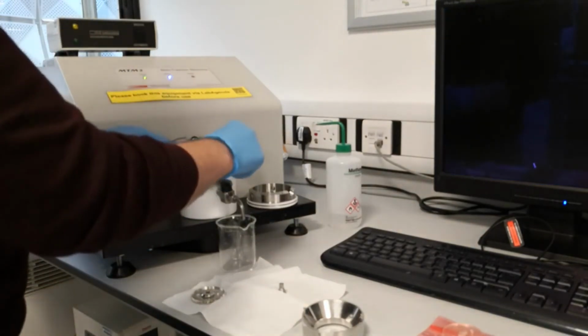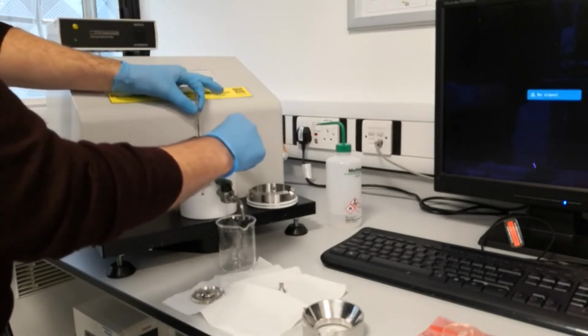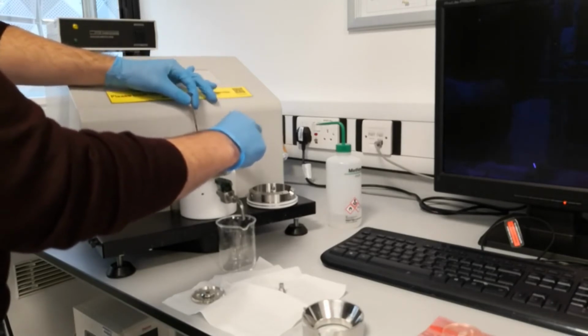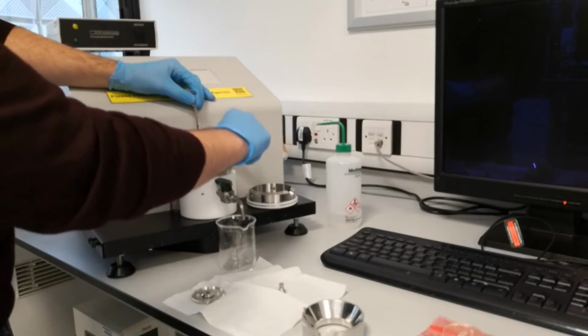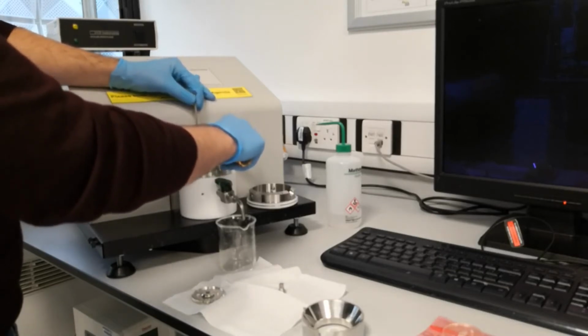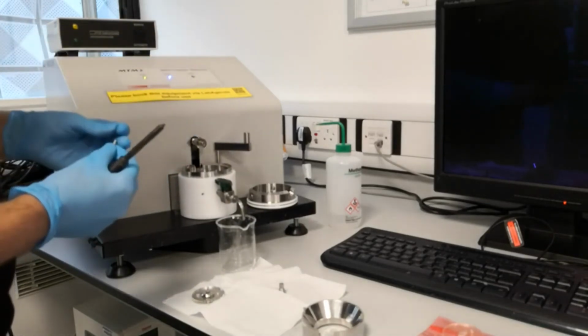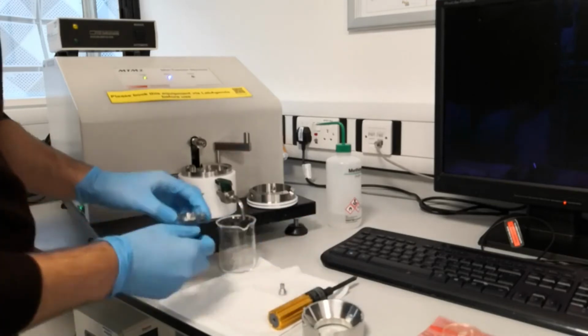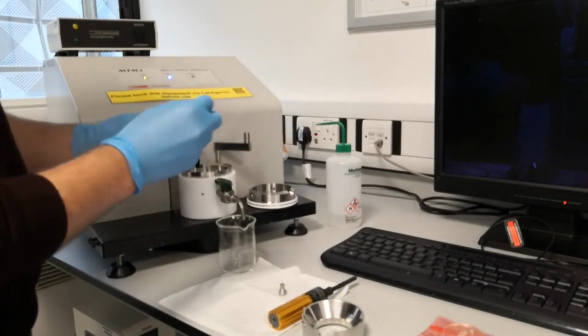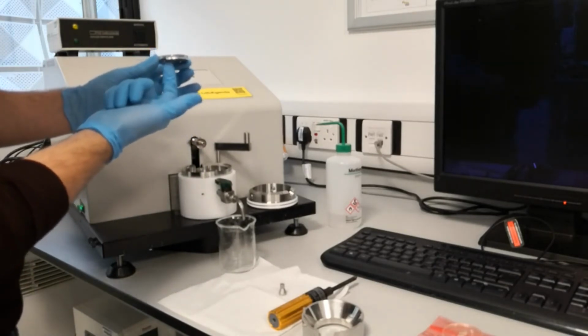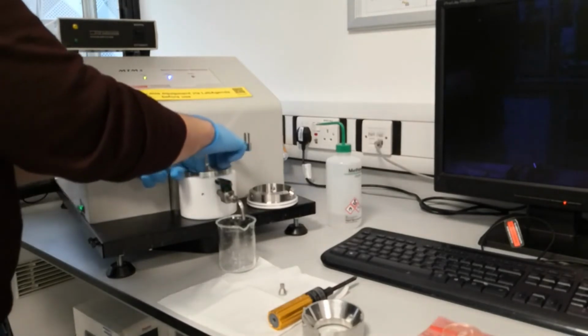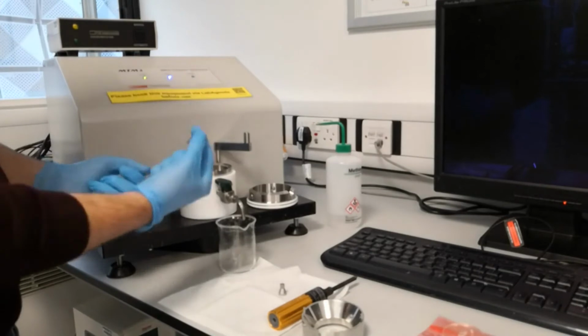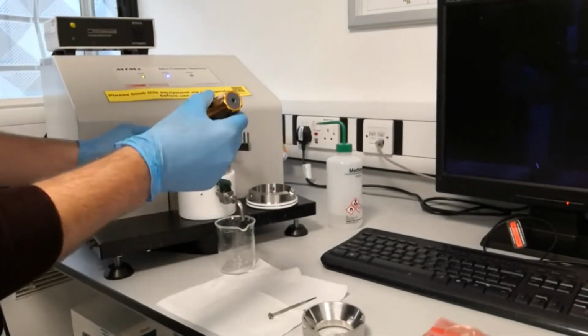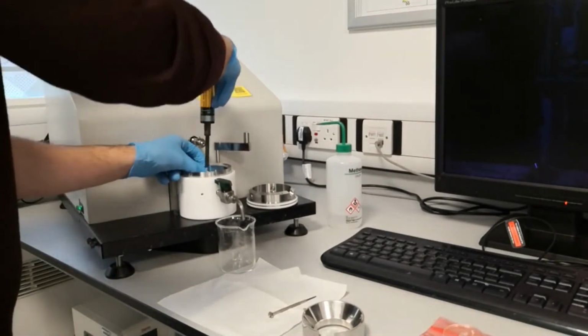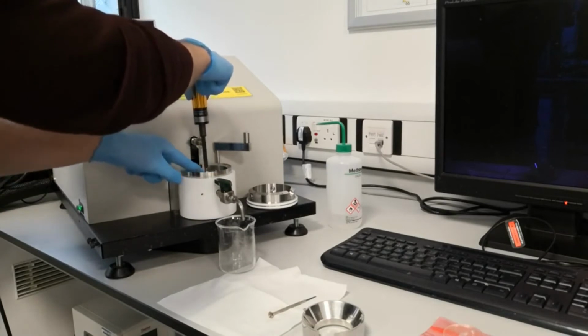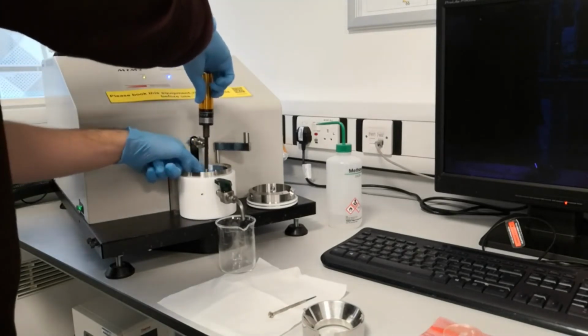To secure your probe, you need to keep the small steel screwdriver stationary and then rotate the screw. You would hear a click. As long as you hear this click, your sample is tight enough and you can carry on mounting your disc. As I mentioned, your disc sits on a retaining steel disc and it goes into the machine. The machine has two pins, with the holes in the retaining disc sitting inside those pins. Then you use the screwdriver with the securing nut to tighten your sample.